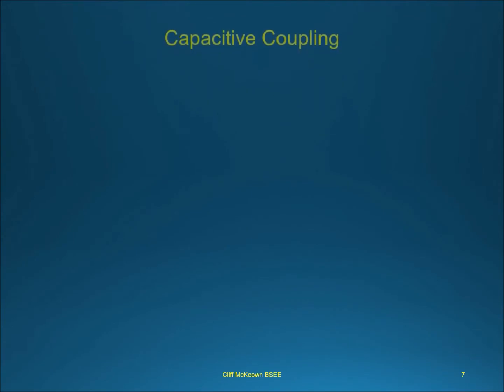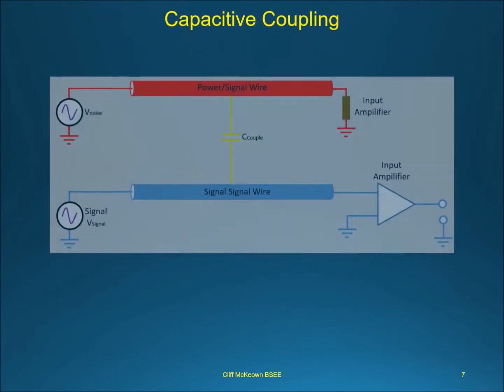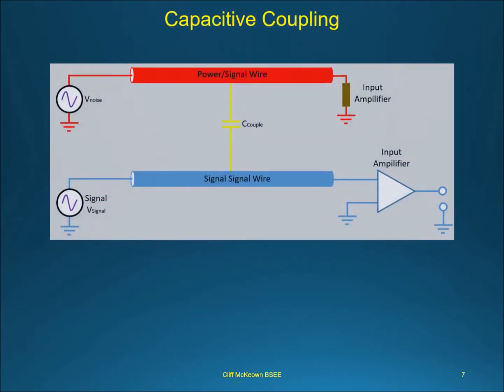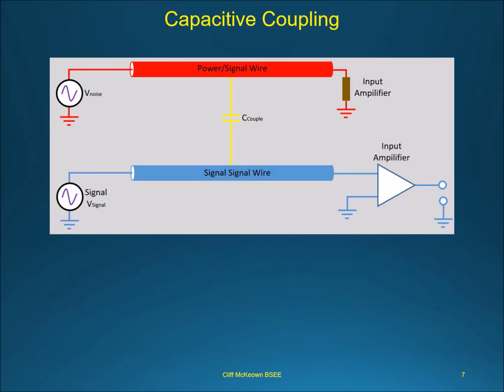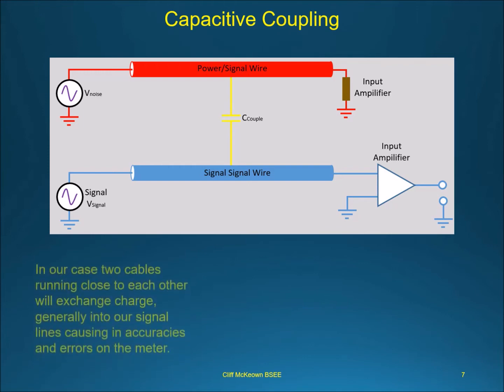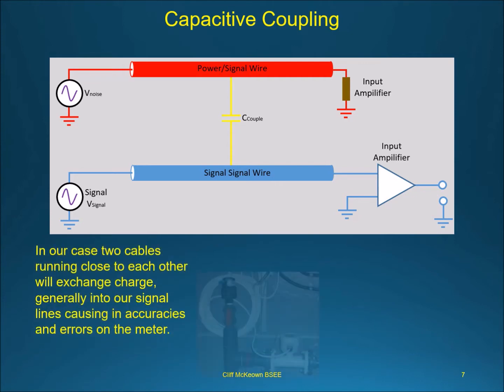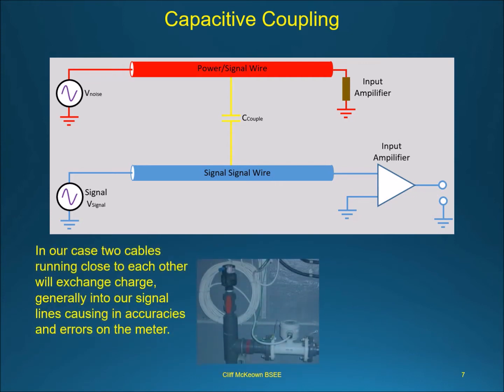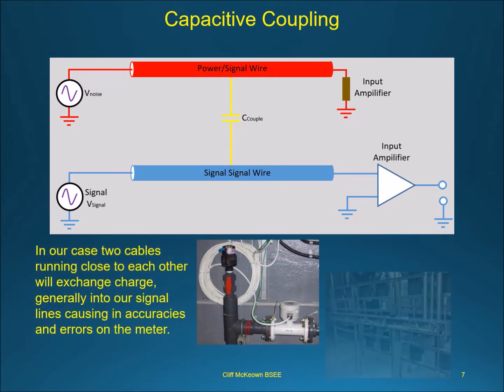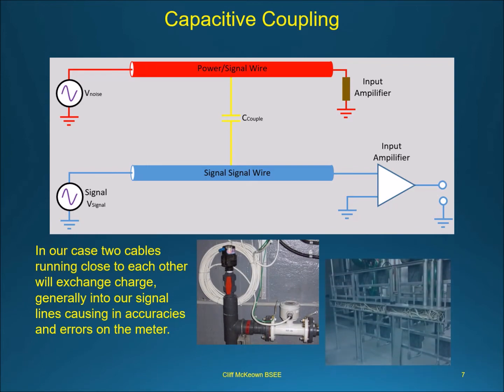In our case, two cables running close to each other will exchange charge, generally into our signal lines, causing inaccuracies and errors on the meter. Coiling cable is essentially creating an ideal coupling — both capacitive and inductive — which results in inaccurate readings and false errors.